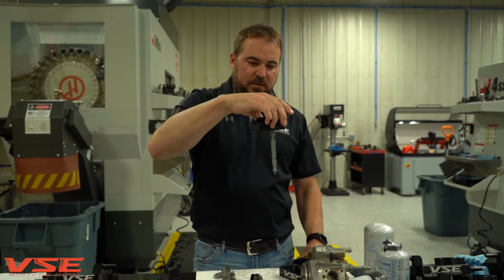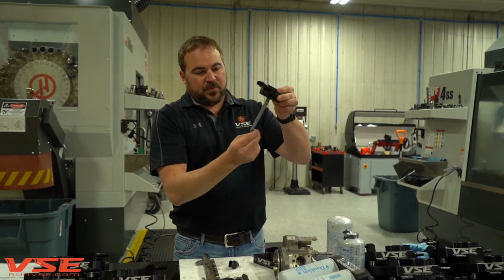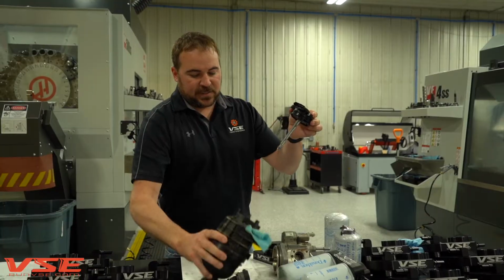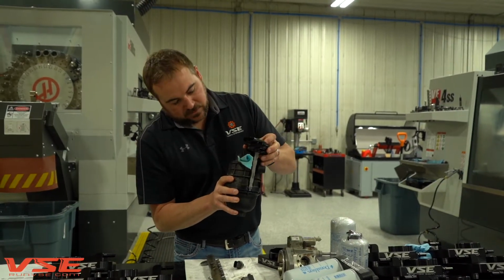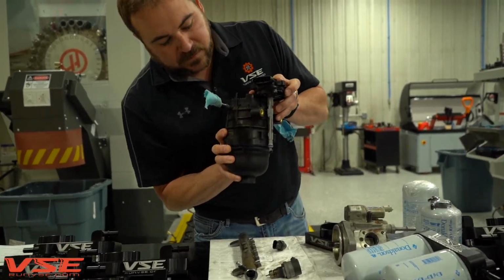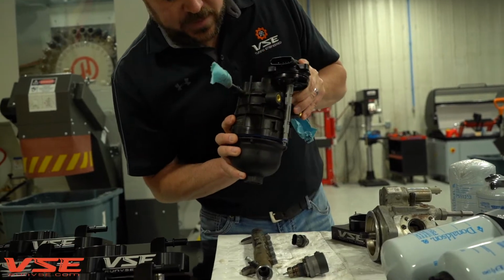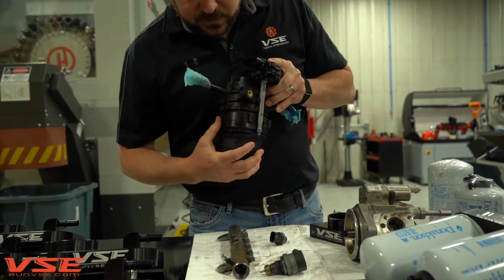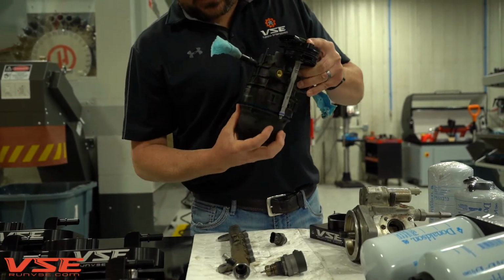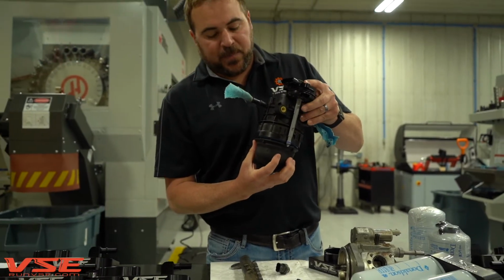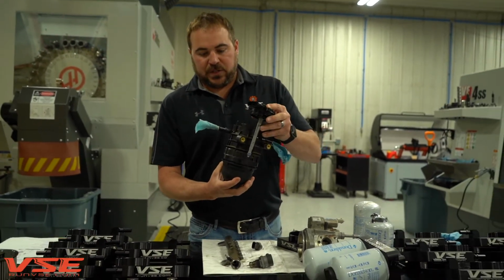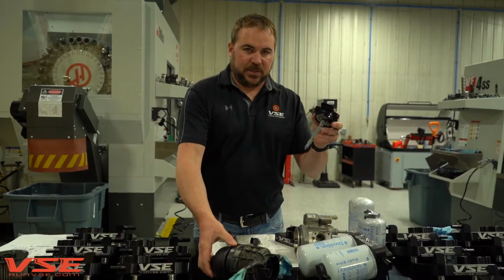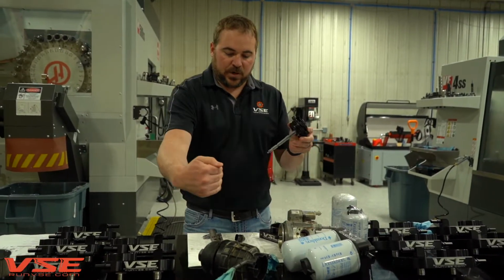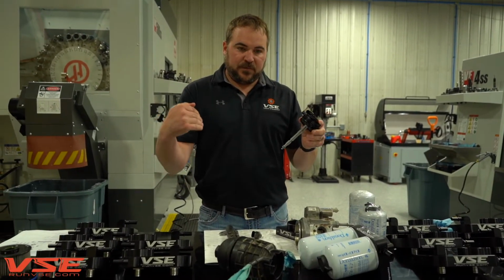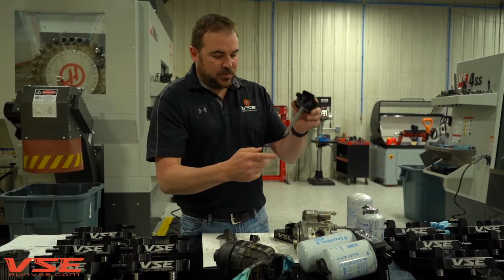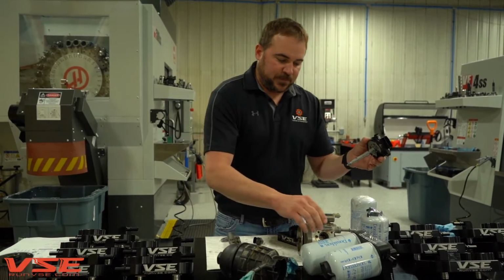So if you take this conductivity probe and it sits down inside this bowl, it looks about like this. So you can see how far down into this bowl this sits. It almost sits right down at the bottom of the filter. And since water is quite a bit heavier, specific density wise, than fuel, the water tends to sit on the bottom of the filter. So this probe would pick up water really quick.